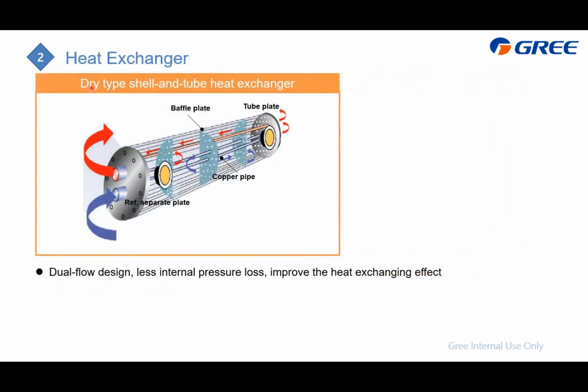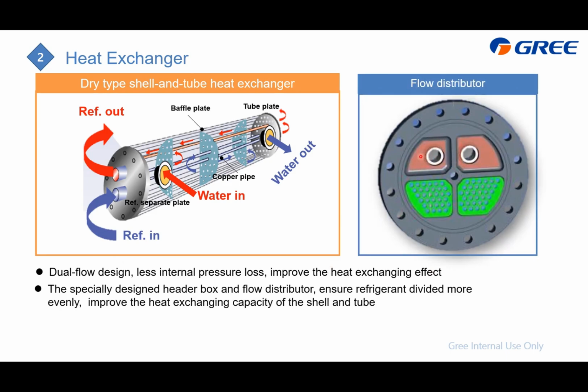Heat exchanger. First is the dry shell and tube heat exchanger. This is for refrigerant to water. You can find that here inside is the refrigerant, and it will cool down the water and exchange heat with the water, and then flow out from here. The refrigerant flows inside the tubes. As for the water, it is inside the shell, outside of the tubes, getting in from here and coming out from here, and they exchange heat inside. And for this one, the internal pressure loss is little, which can improve the heat exchange effect. We also have this structure to ensure the refrigerant is divided evenly into the different tubes.